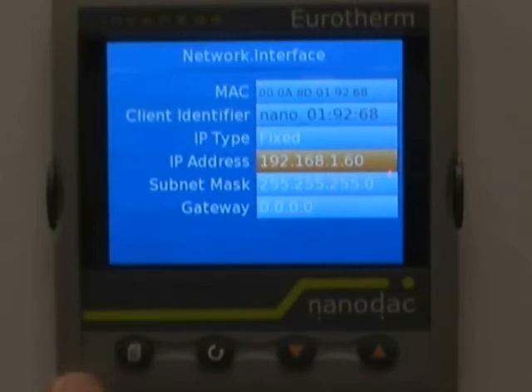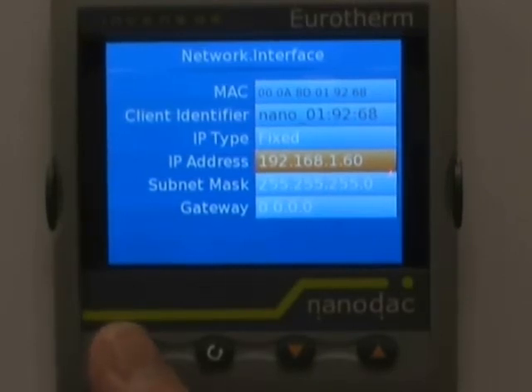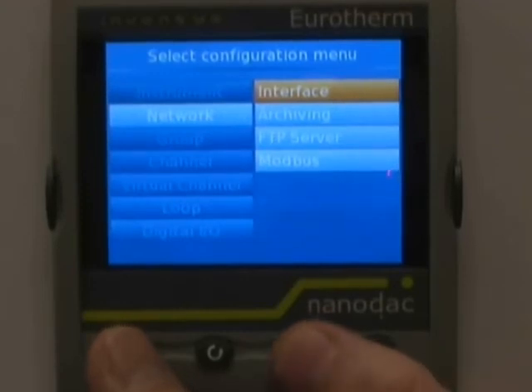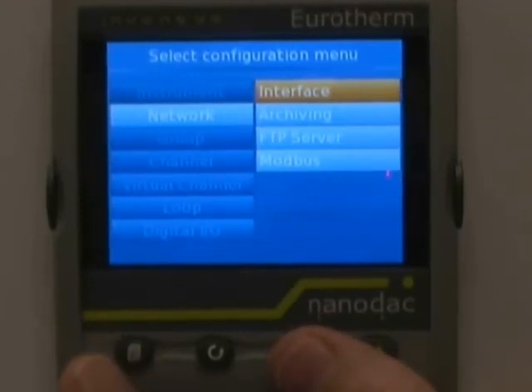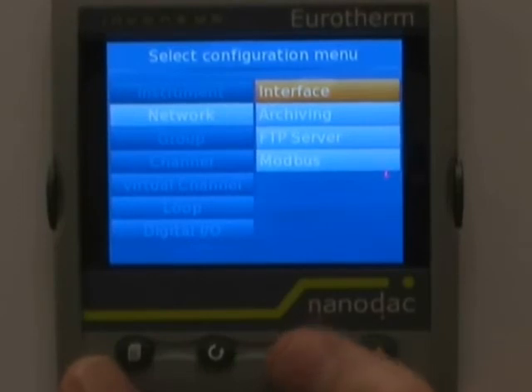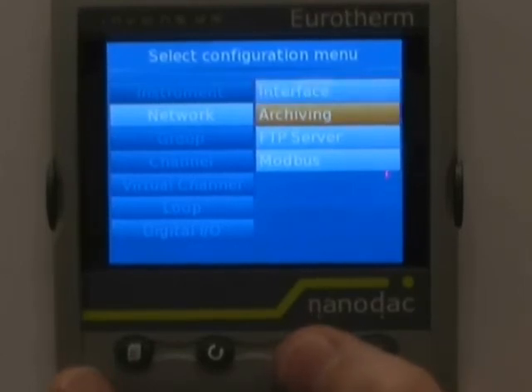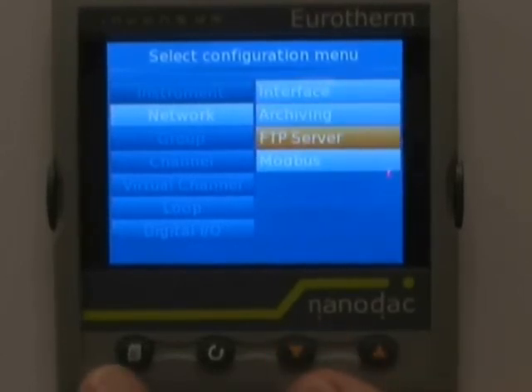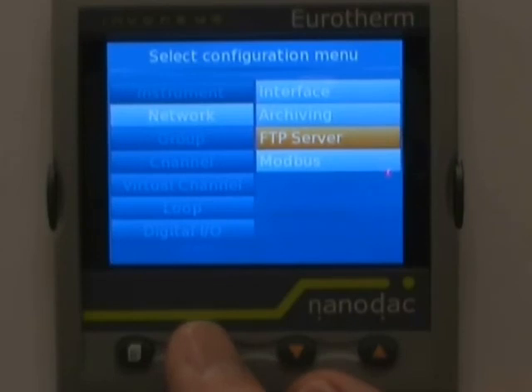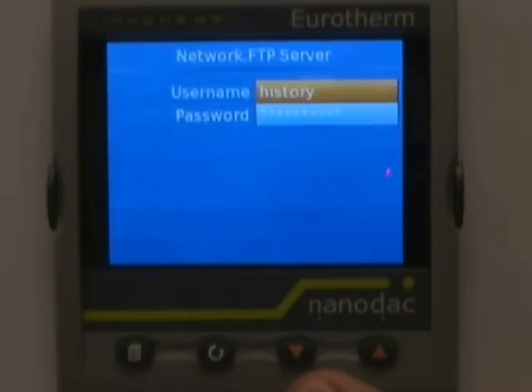From here we're going to change the FTP server password to 100. This is critical for use in the review software, as shown in a further video tutorial. We hit the page key once to back up to the select configuration menu, hit the down arrow to FTP Server, and with it highlighted, hit the scroll key once.